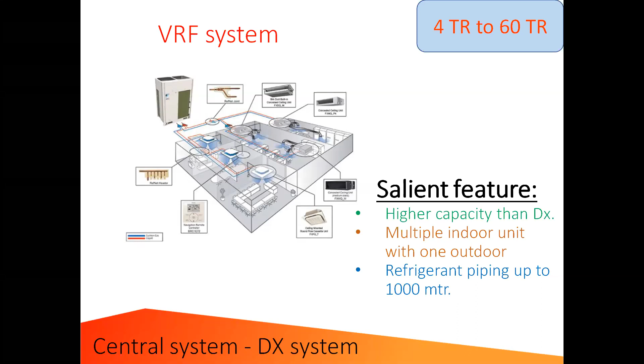The third benefit is variable refrigerant flow. What this means is, when you design your system, you design it for peak capacity, assuming outside temperature is 43 degrees and you're maintaining 23 to 24 degrees inside the room. But that's not always the case. In the morning, evening, night hours, or in months like March, August, September, the outside temperature is not 43 or 44 degrees. So your compressor, which was designed for 2 tons, may not require 2 tons capacity at that time; it may only require 1 ton. In a VRF system, the compressors are designed to run on variable capacity, so they run at reduced capacity and consume lower power. That's why they are more energy efficient compared to normal split ACs.